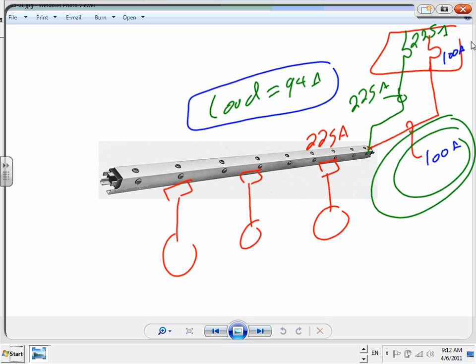Any questions, guys, about the trolley busways? Everybody knows how to size them. Brad, right? We know how to size them. If they were feeding motors, we take the largest motor multiplied by 1.25 plus all the other motors, and we go to the cable and pick the size that can give us this amount of amps, right? Like we did with Chad, and we put the overcurrent protection device, your option.